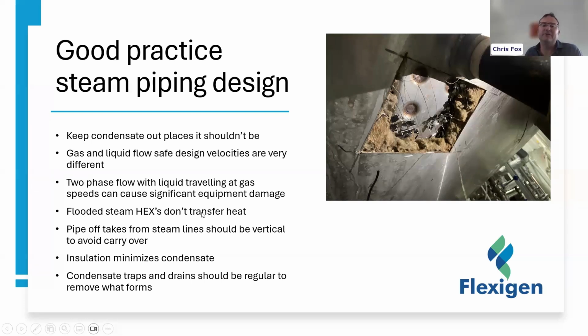Flooded heat exchangers don't transfer heat. So if your steam traps aren't working and your heat exchanger is half full of condensate because it's not getting away, you've lost half your heat transfer area. Your heat exchanger is only going to give you half of the heating it should.